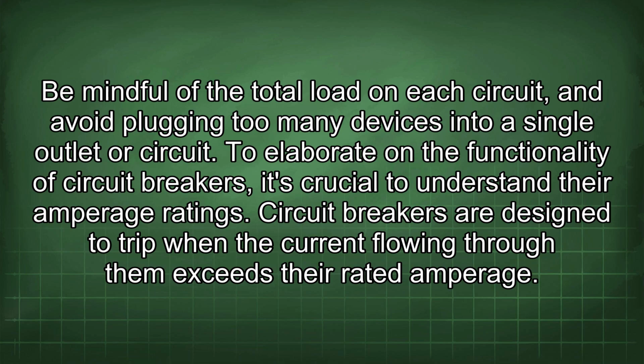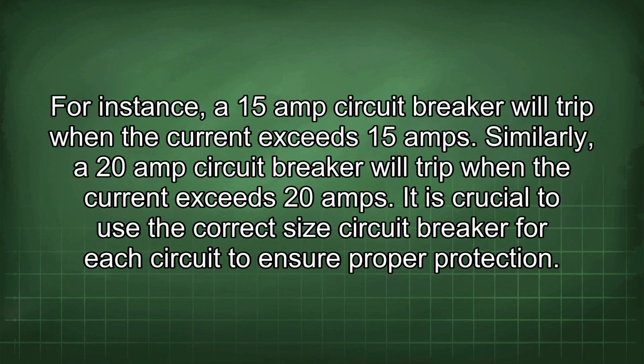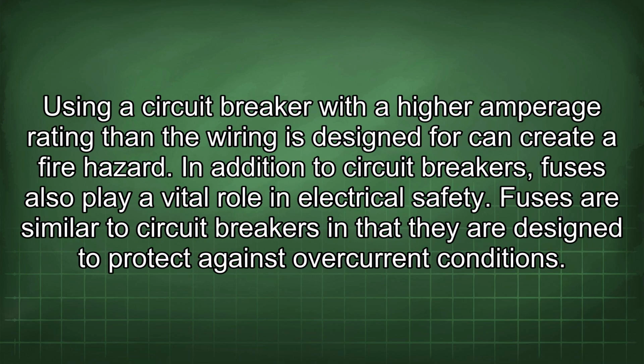To elaborate on the functionality of circuit breakers, it's crucial to understand their amperage ratings. Circuit breakers are designed to trip when the current flowing through them exceeds their rated amperage. For instance, a 15 amp circuit breaker will trip when the current exceeds 15 amps. Similarly, a 20 amp circuit breaker will trip when the current exceeds 20 amps. It is crucial to use the correct size circuit breaker for each circuit to ensure proper protection. Using a circuit breaker with a higher amperage rating than the wiring is designed for can create a fire hazard.